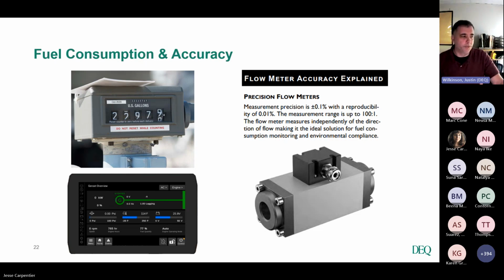Most of our facilities were using electronic control modules to monitor their fuel throughput. When we started looking into the accuracy of those monitoring devices, we saw that they're not 100% accurate and there is some fluctuation. Early on, when we started asking this question, it was very difficult to get manufacturers to guarantee their ECMs. So in some of our site evaluations, testing, and research, we determined that plus or minus 5% is what we would typically see for ECM accuracies for fuel throughput.